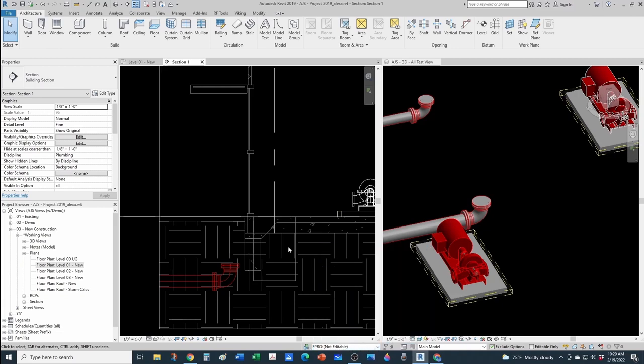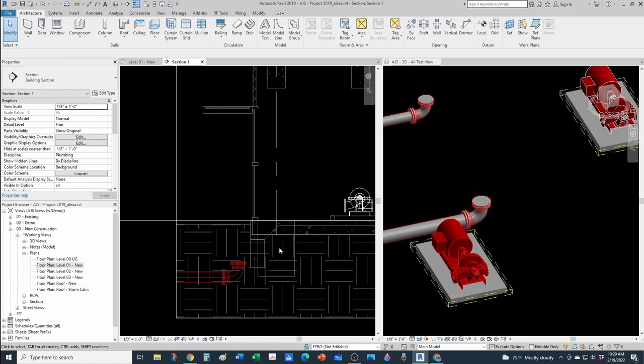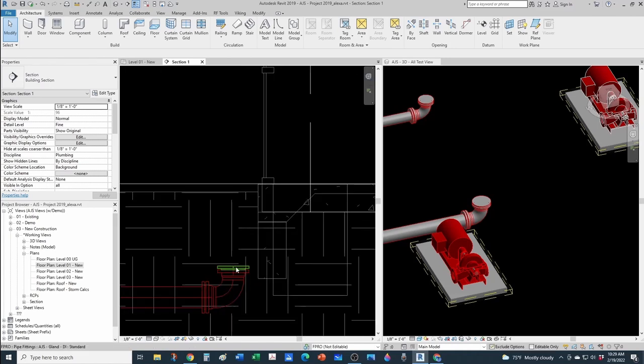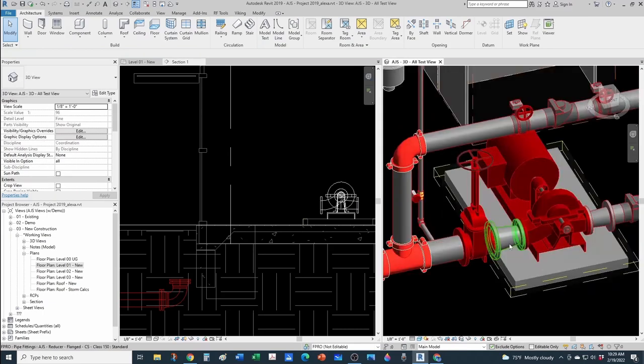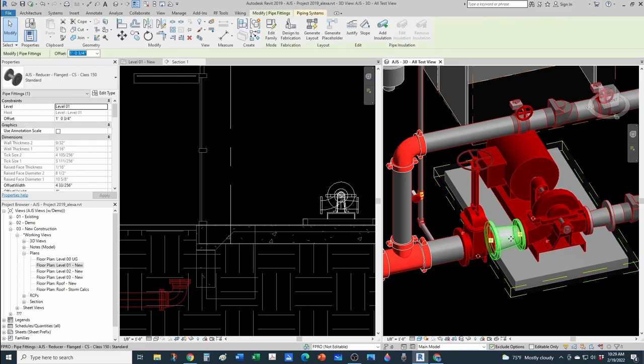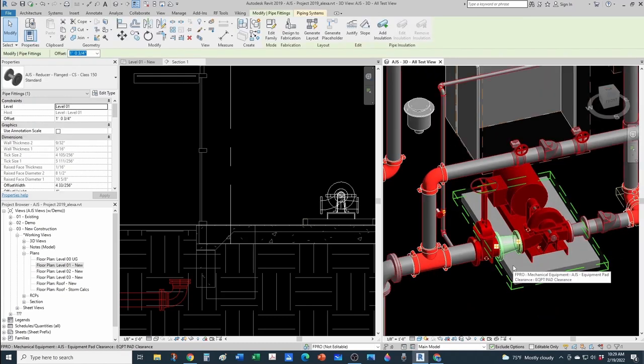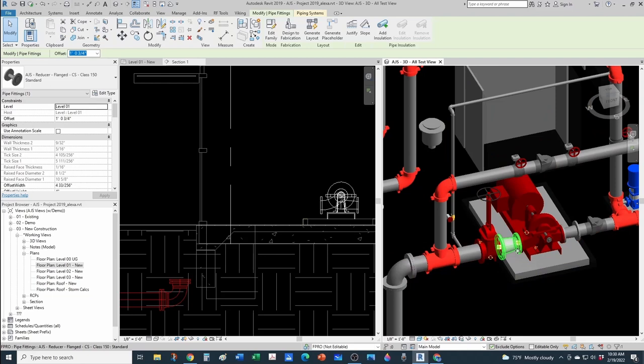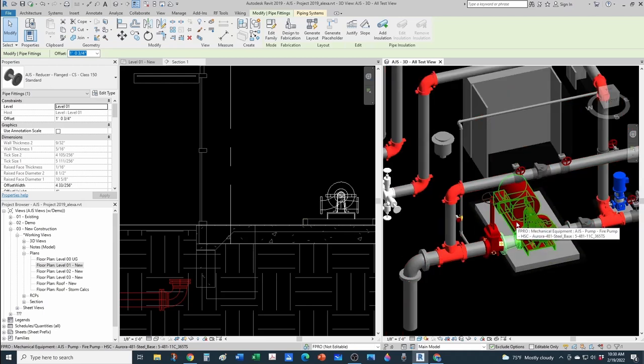In this case, this is a combined plumbing / fire protection model, so I have both there. In my library, I don't have a reducer that is of the eccentric type. So what I do is I use a concentric reducer and I make sure that I label in my plans, I call for an eccentric reducer. And obviously I have a full detail of a fire pump where I specify everything that's required there, because you need to be practical about what you are designing and drafting and what you're calling for, just in a detail to get things done. Otherwise you'll never finish.